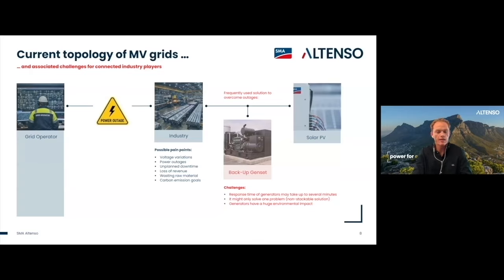And that results in unreliable power supply. And so this would also be exacerbated by large inductive loads that you might have on site, like motors and drives, which create a lot of harmonics in the system.